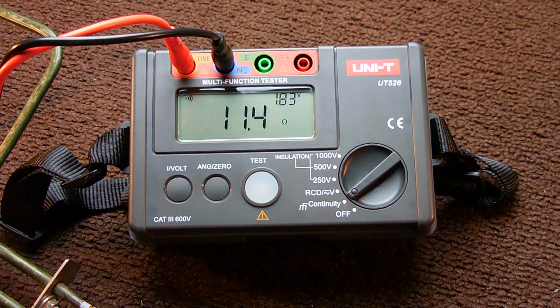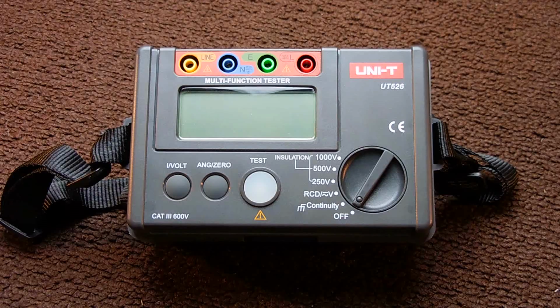So not only would you use this for protective earth conductors, you can use it for measuring resistance up to 2 kilo ohms as well. This unit has the ability to measure up to 440 volts, AC or DC. It automatically identifies if it's AC or DC, and it'll also give you a frequency readout between 20 Hertz and 100.